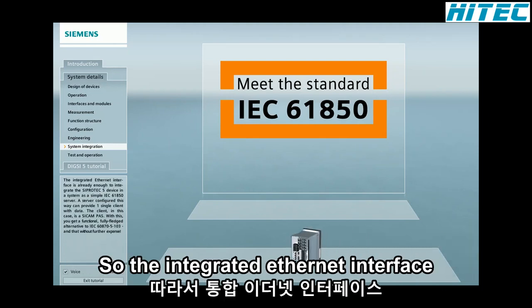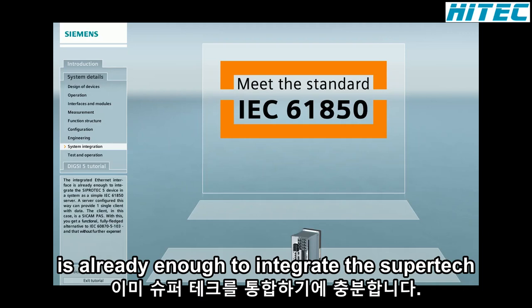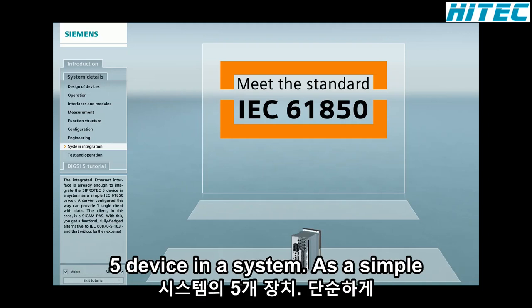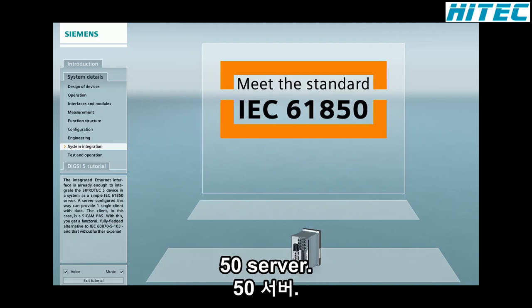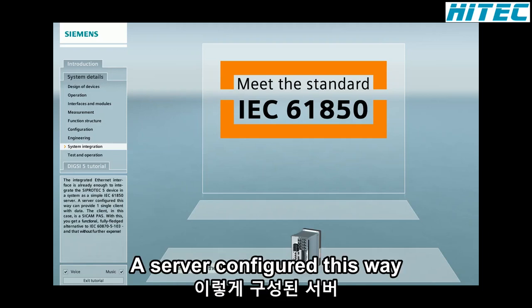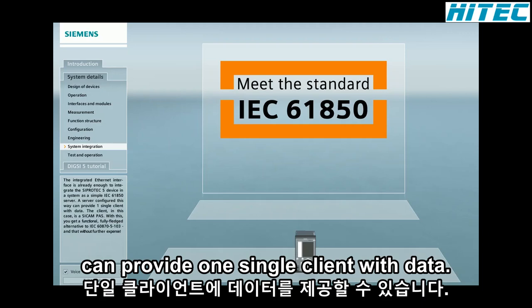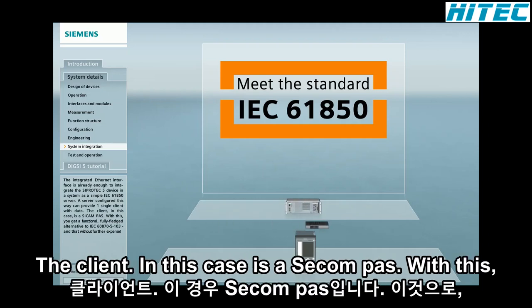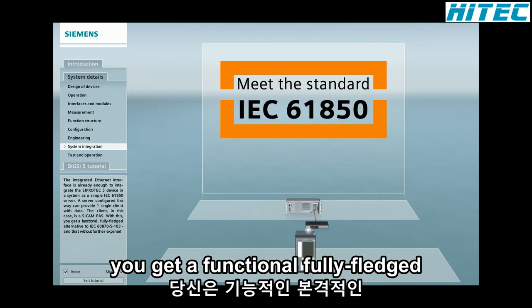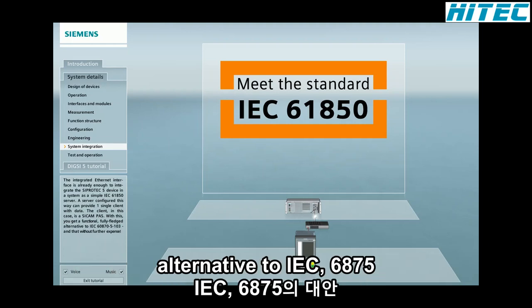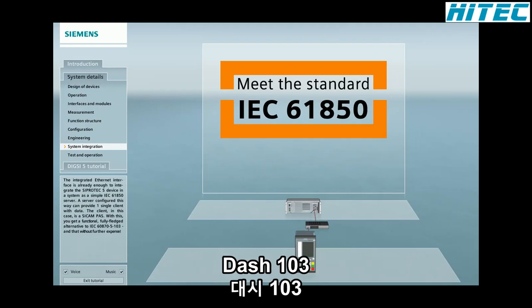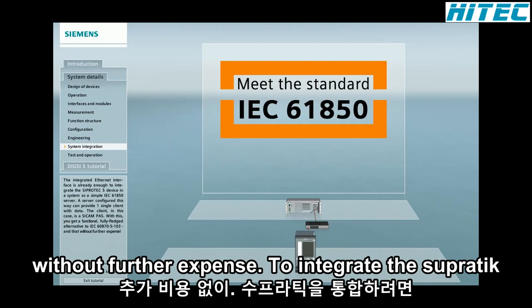The integrated Ethernet interface is already enough to integrate the SIPROTEC 5 device in a system as a simple IEC 61850 server. A server configured this way can provide one single client with data. The client in this case is a SICAM PAS. With this, you get a functional, fully fledged alternative to IEC 60870-5-103, and that without further expense.